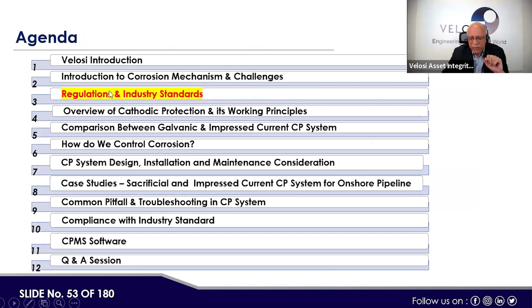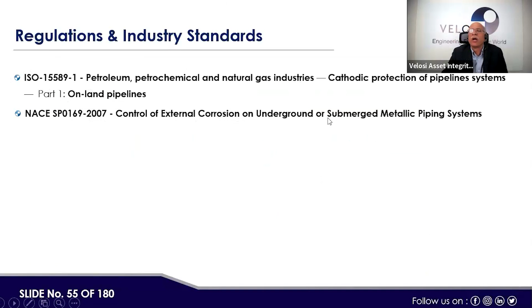Now the main two standards we want to cover. There are other standards as well, but the main standard used as a basis for the CP system is ISO 15589-1, for petroleum, petrochemical, and natural gas industries, covering cathodic protection of pipeline systems like on-land pipelines. Then NACE SP0169-2007, for control of external corrosion on underground or submerged metallic piping systems.